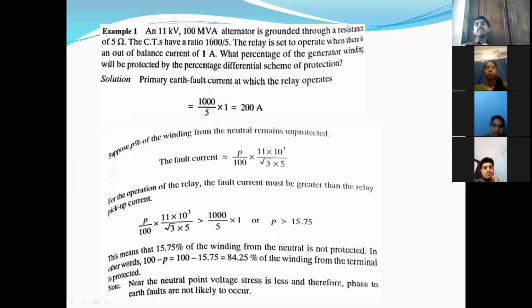An 11 kV, 100 MVA alternator is grounded through a resistance of 5 ohms. That means the Rn value is given. The CT ratio is 1000 by 5. The relay is set to operate when there is an out of balance current of 1 ampere. What does 1 ampere mean? Out of balance current means secondary current.